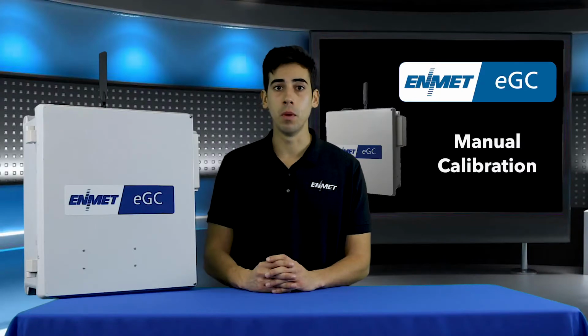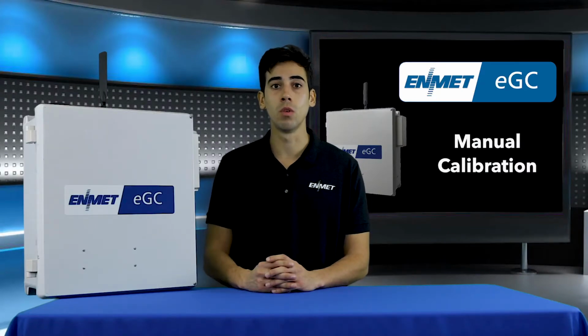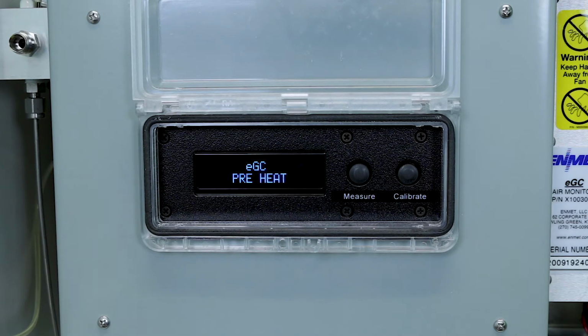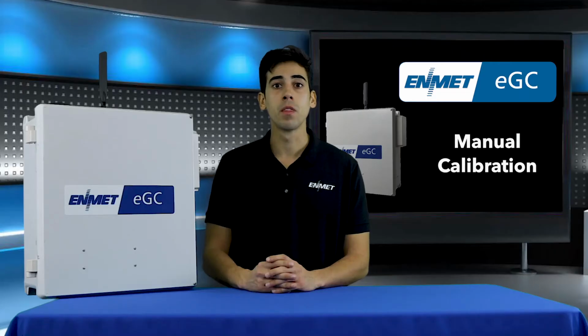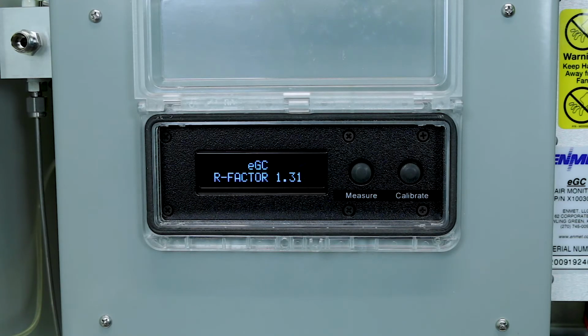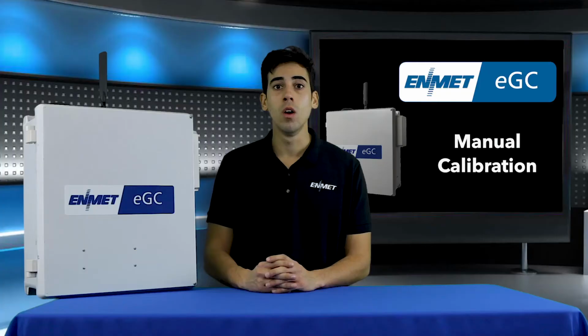Once you press the calibrate button, the eGC will display the following screens during its measurement cycle: sampling, preheat, sample inject, purge, and system run. Once the measurement is complete, the results will be displayed on the screen until the next measurement begins. The calibration of the eGC will occur at pre-programmed intervals. ENMET's eGC units are preset to calibrate 4 times every day. This completes the manual calibration process of ENMET's eGC.